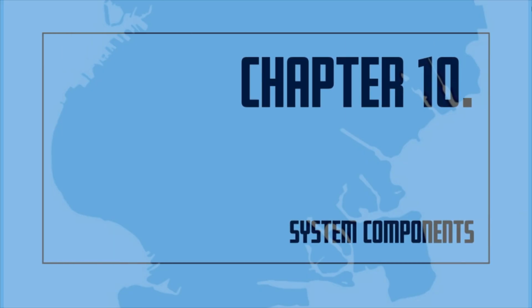Chapter 10. System components. Sprinkler heads. Sprinkler heads are made of metal. They are screwed into the piping at standard intervals. The water is prevented from leaving the sprinkler head by an arrangement of levers and links. The levers and links are soldered together on the sprinkler head. The solder is a metal alloy with a fixed melting point. Other types of sprinkler heads use a glass bulb which expands and breaks under heat. The sprinkler head is factory tested to withstand at least 400 psi without injury or leakage. If properly installed, there is little danger of the sprinkler operating unless it is damaged.